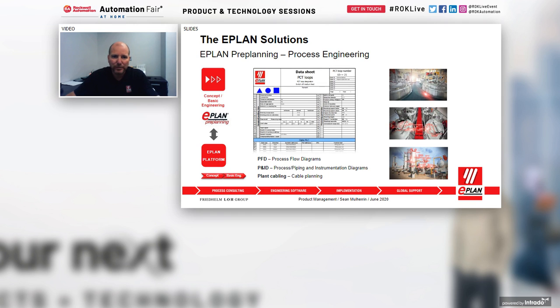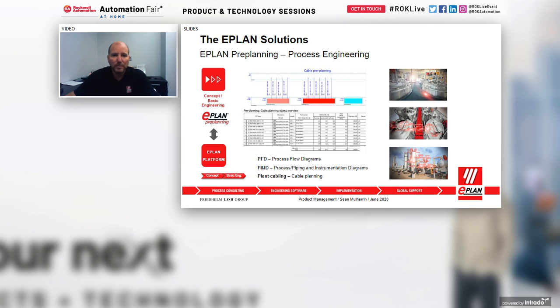EPLAN Pre-planning in process engineering also allows a user to generate data sheets. Data contained in the instrumentation, such as minimum values, maximum values, what type of environment the process is going to take place in, and certain requirements, can all be captured in a data sheet. These data sheets can be used as order forms for ordering the components from various manufacturers such as Endress+Hauser, an Encompass partner of Rockwell. We can also manage cables. If you have cabling requirements and need to capture cable information between various sensors or instruments and the controllers right up front in the planning phase, you can do that using EPLAN Pre-planning.